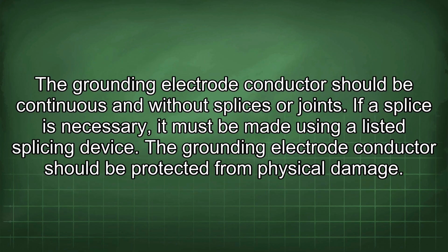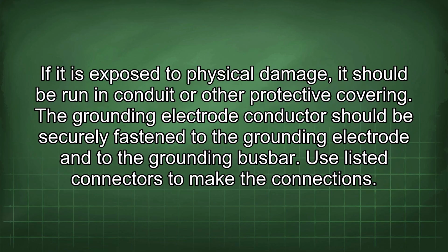The grounding electrode conductor should be continuous and without splices or joints. If a splice is necessary, it must be made using a listed splicing device. The grounding electrode conductor should be protected from physical damage. If it is exposed to physical damage, it should be run in conduit or other protective covering. The grounding electrode conductor should be securely fastened to the grounding electrode and to the grounding busbar. Use listed connectors to make the connections.